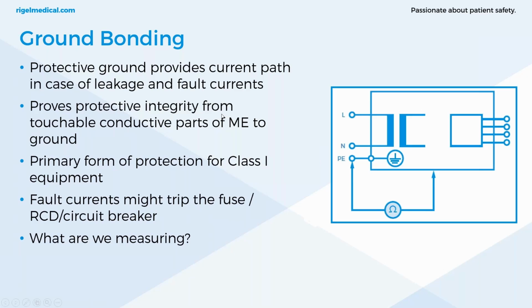It proves protective integrity from touchable conductive parts of the medical electrical equipment to ground. And routine testing of earth bonding is just to ensure adequate connection between these conductors and the mains plug. So we've got good grounding between the protective earth and any exposed connections.